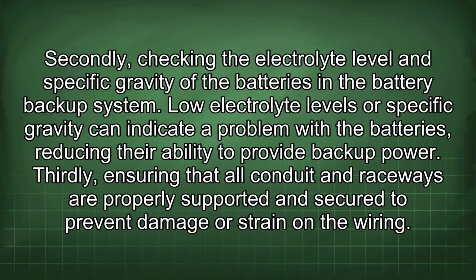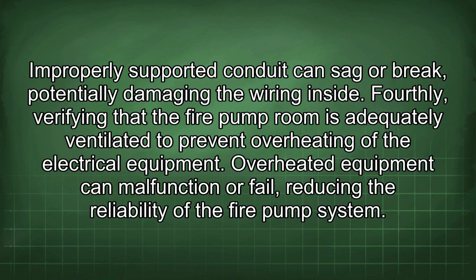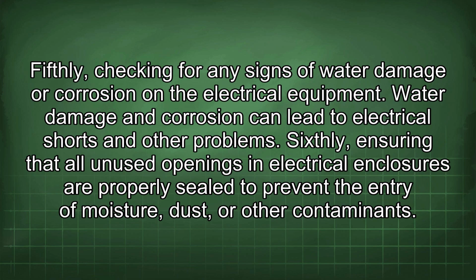Thirdly, ensuring that all conduits and raceways are properly supported and secured to prevent damage or strain on the wiring. Improperly supported conduit can sag or break, potentially damaging the wiring inside. Fourthly, verifying that the fire pump room is adequately ventilated to prevent overheating of the electrical equipment. Overheated equipment can malfunction or fail, reducing the reliability of the fire pump system. Fifthly, checking for any signs of water damage or corrosion on the electrical equipment. Water damage and corrosion can lead to electrical shorts and other problems.